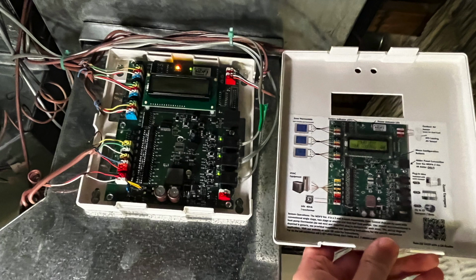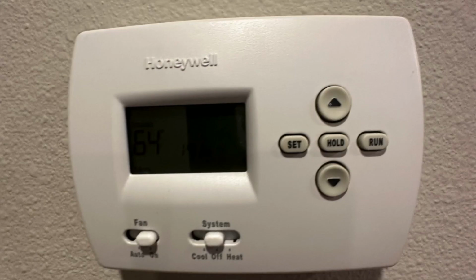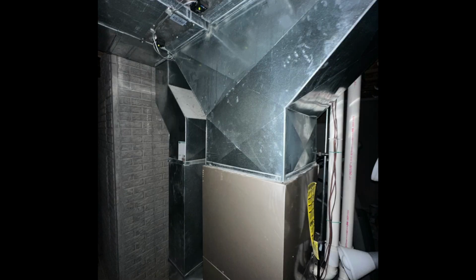They're different every time. For the case of my house, I have a Zone First system. So I didn't have to actually change out any thermostats, but what I did have to do is change the Zone First system from an air conditioning mode to a heat pump mode. So the contractor happened to be very familiar with Zone First systems. He changed a couple of boards and voila, we're back in business with the same existing room thermostats, the same existing dampers, and the same existing control box with the board changed out.